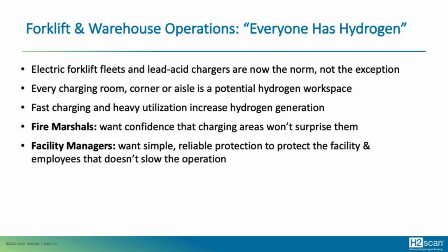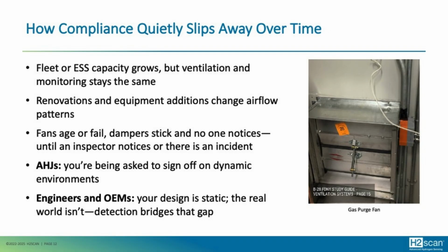So with forklift and warehouse operations, just keep in mind, if you're charging batteries in forklifts, you have hydrogen. And so it is our responsibility to make sure we're mitigating these risks, and also the fire marshal and the facility manager kind of work together in making sure that the proper systems are installed and maintained properly. So as we renovate and add equipment and changes, we have to make sure our airflow patterns are correct, and that we have proper mechanical ventilation and detection. And as fans age or fail, we have to make sure that those are maintained and replaced as well before there's an incident. So making sure that our equipment is in the proper life cycle is very important.